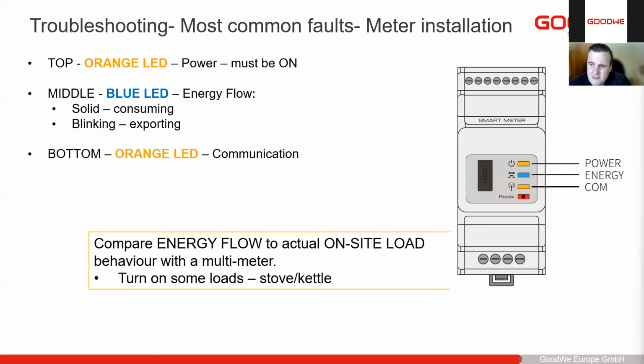And then lastly is the communication LED, to see whether it's communicating with our inverter. If it's blinking, it's transmitting data. The reset you will only see if the reset button is pressed, but normally we do not use the reset button. And it's always good to compare the energy flow on site with your multimeter. If you have a clamp tester, look at PV Master, clamp test, switch on fixed loads so that you know more or less what the load will be drawing, and make sure that everything there is correct.